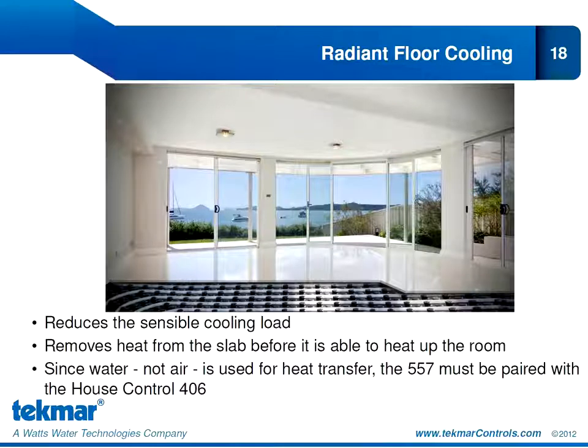Radiant floor cooling will reduce the sensible cooling load. It is not intended to provide 100% of the cooling because it cannot remove humidity, or as we call it, the latent heat load. It can only address the sensible cooling load. Now, numbers that are tossed around in the industry, a conservative estimate would be 5 to 10 BTU per square foot of cooling capacity. But if we're in an area like the one we've shown here where there is a lot of window space, a room that's going to experience a lot of solar gain, our cooling capacity can actually reach 30 to 35 BTU per square foot.